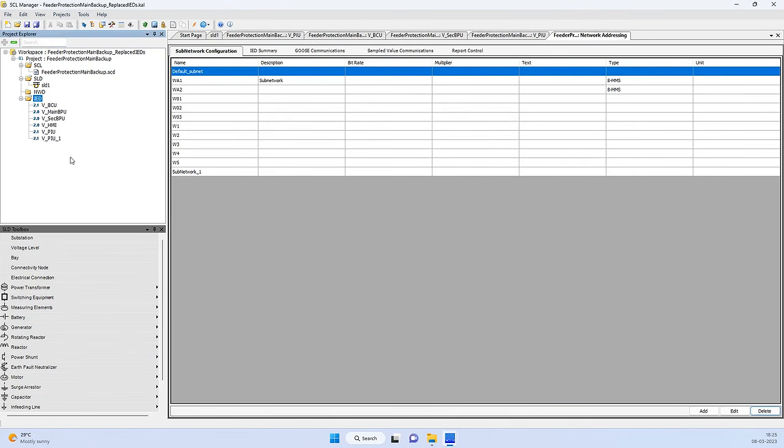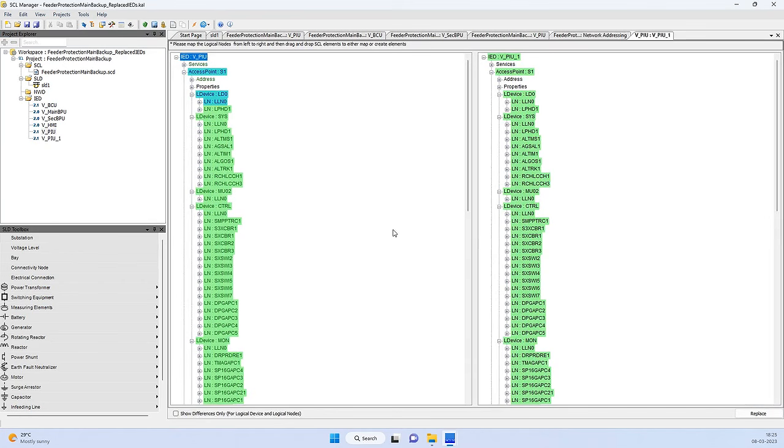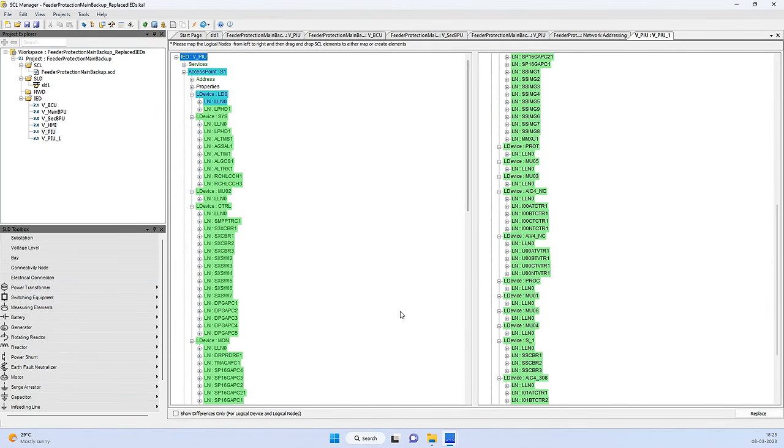So I finish. Now I have my vPIU1. So I take my real PIU and I'm planning to replace it with the new version which has come back from the IED programming stage, and say okay. Now it's again the same picture because the same structure. We no longer have any problem with the logical data model. You remember the monitor logical device, everything is fine because there's no change between these two data models.